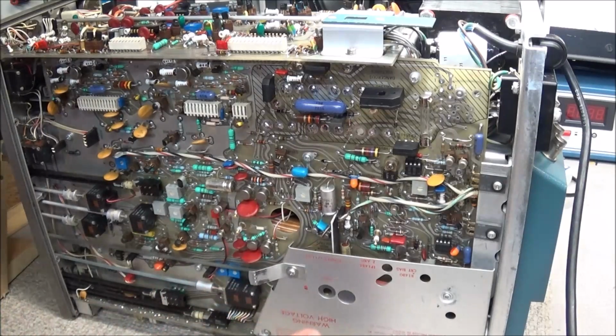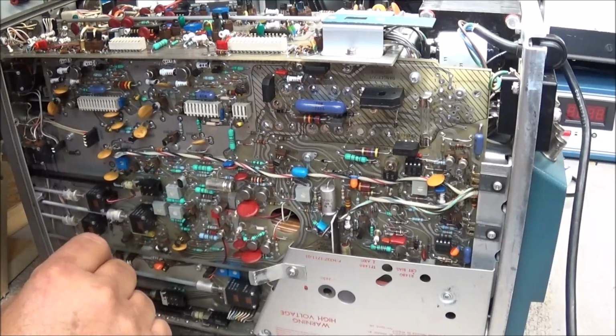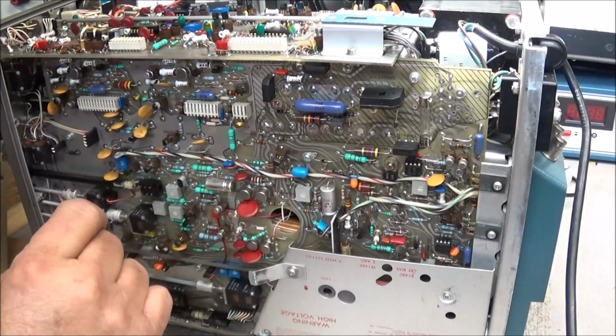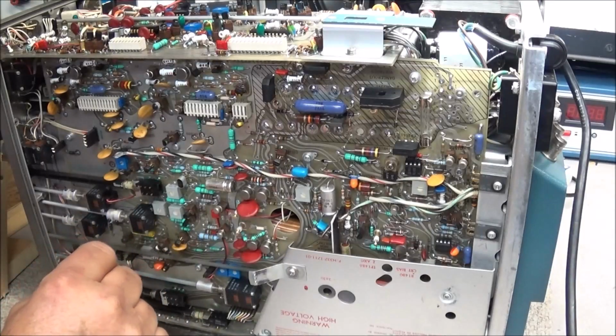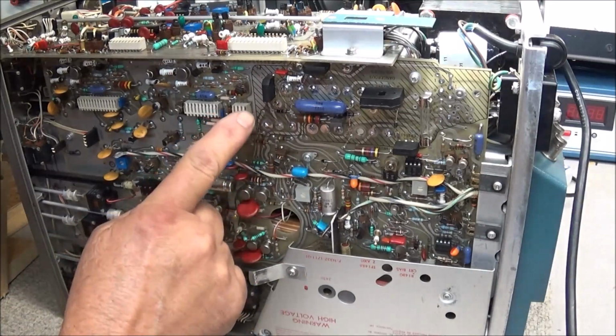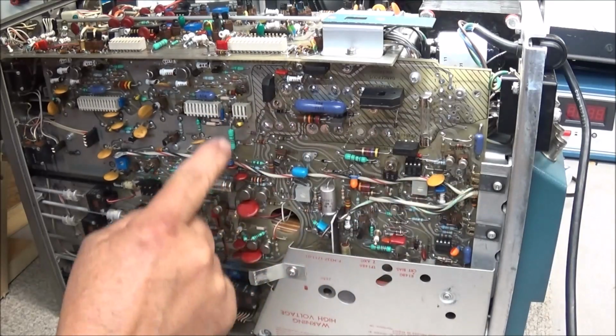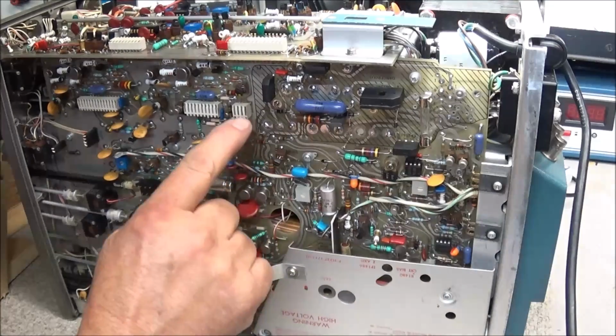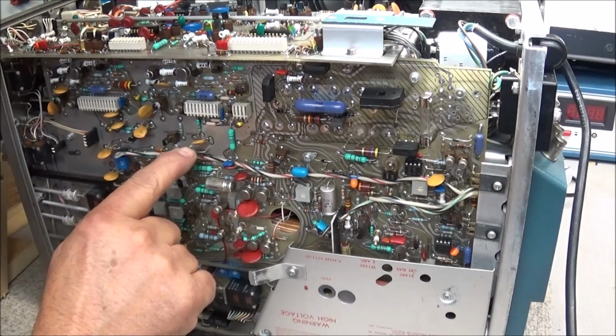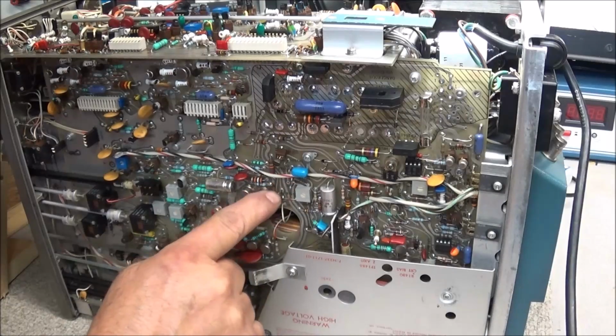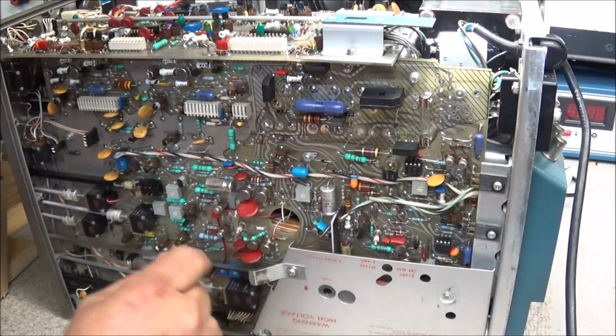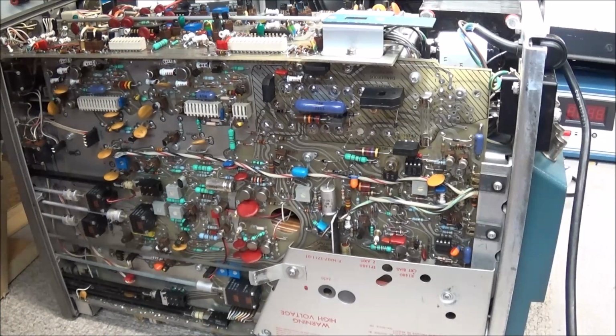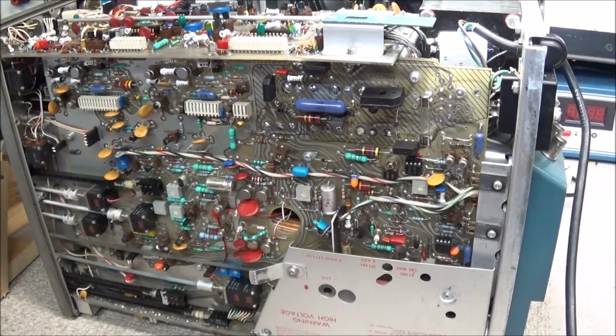So what we're going to do is go ahead and check out the power supply rails, find out which ones are working, which one is not. We can assume that we do have mains voltage coming in, but we do need to check for that to make sure that it is getting mains voltage. If you look here on the bottom, up in this area, this is your power supply, and this is your high voltage section. On low voltage power supplies, you'll see a ground loop here that you can attach to, and then you'll see several pins over here for checking our low voltage supply. So we'll go ahead and start checking and make sure that we do have voltage on this thing.